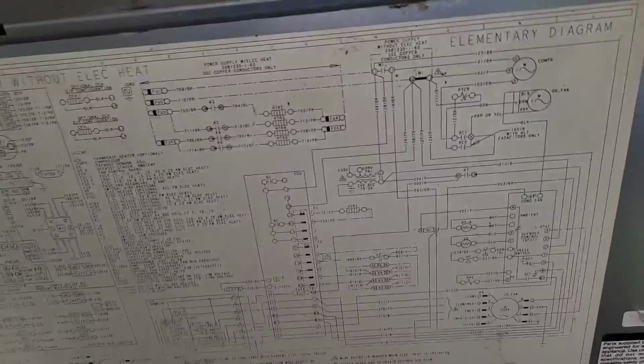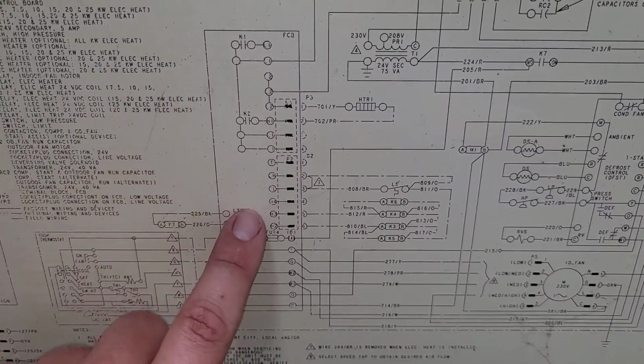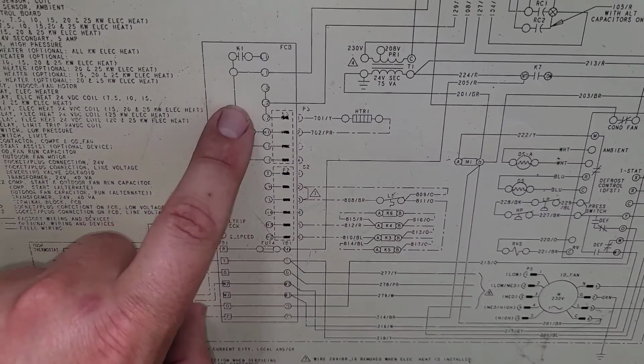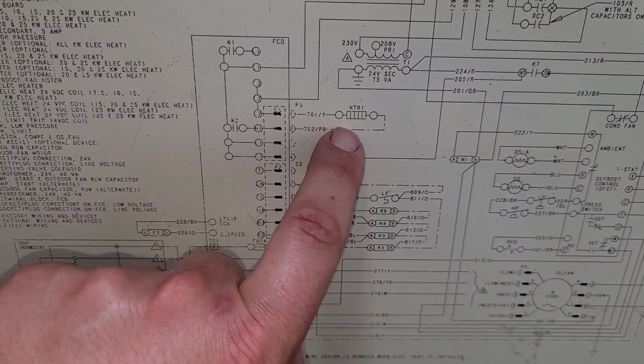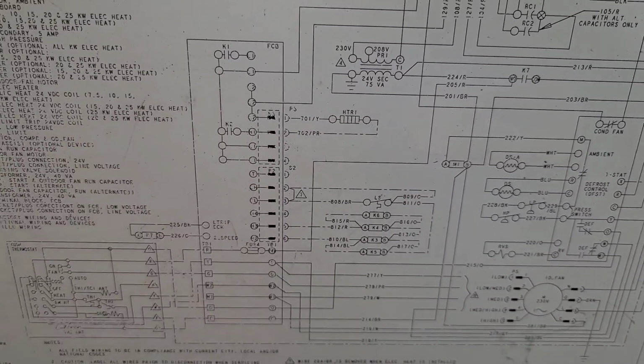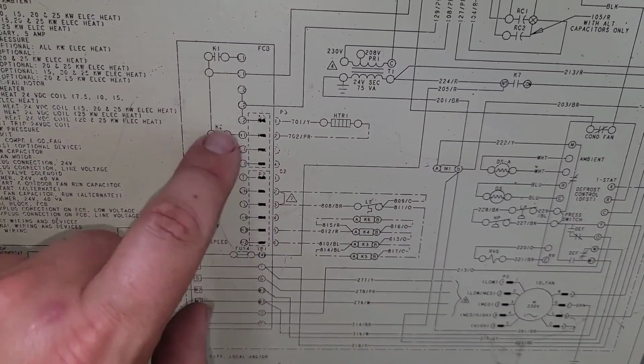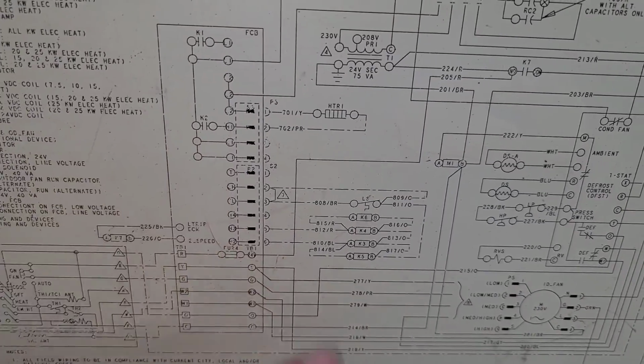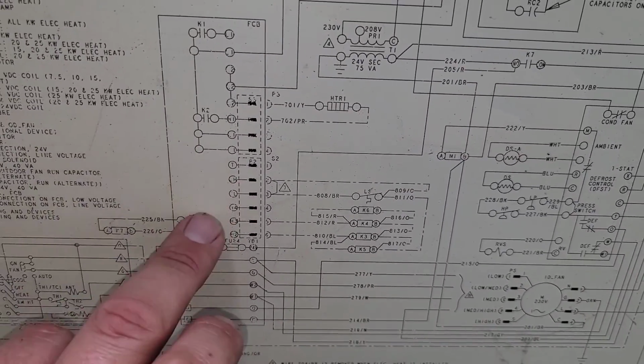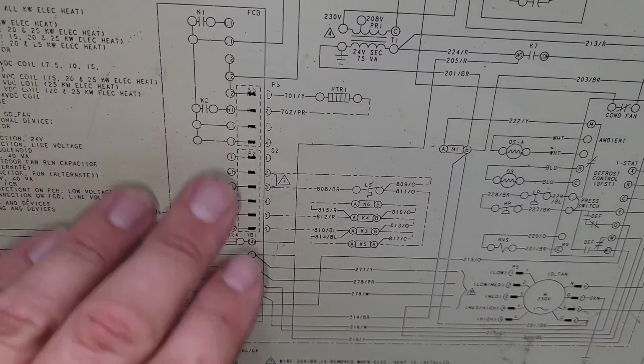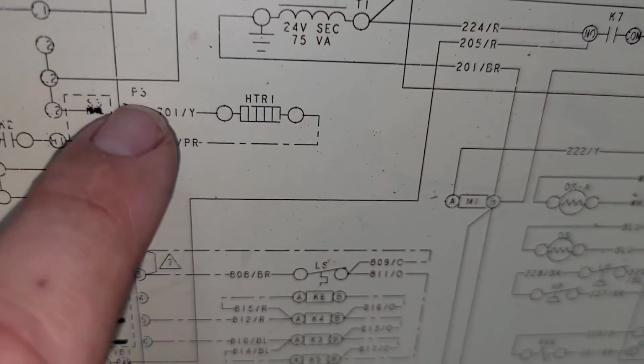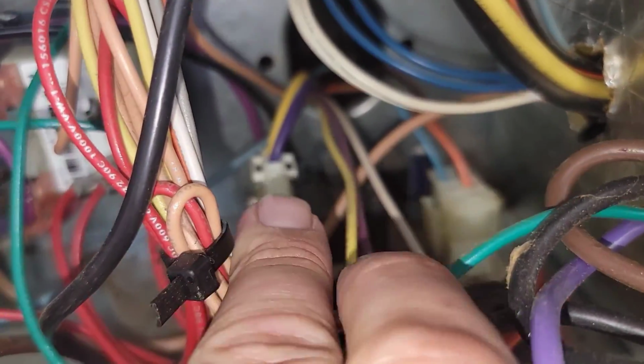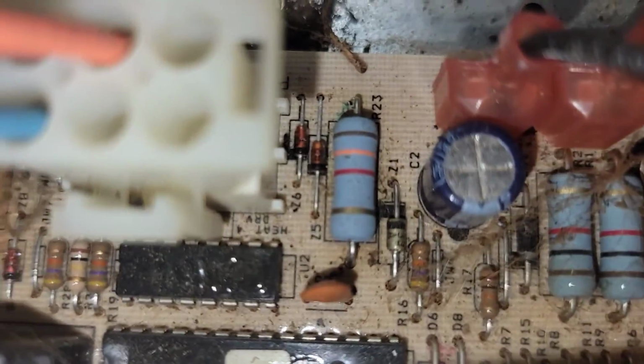Let's see, we got our schematic. Here's our fan control board, the one that controls that heater through that board, which is really not a good idea, because when you have that much current going through a board, I think that's one of the causes of the short life of this board, causing it to burn up. But you can see heater number 1, yellow and purple wire, and that's that right there. Let's just take a look, see if we can see any burn marks at all.